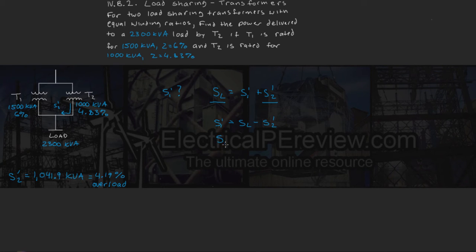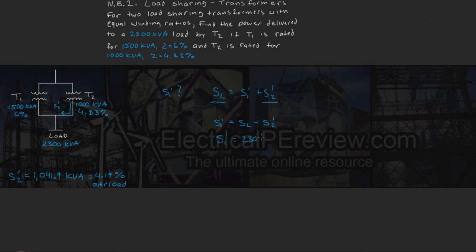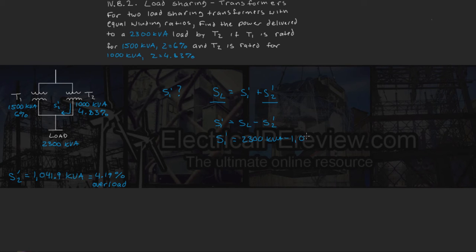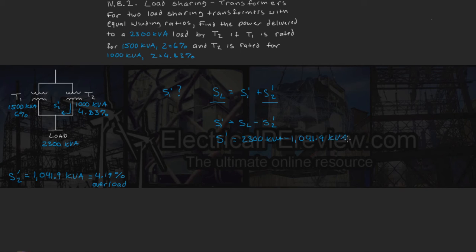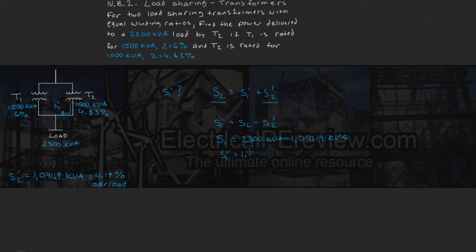So our transformer 1 contribution is the same as 2300 kVA minus 1041.9 kVA. This comes out to be 1258.1 kVA.